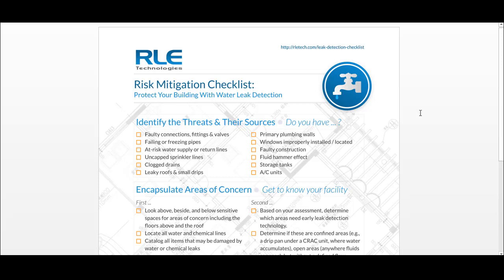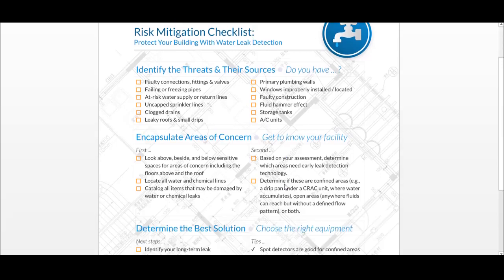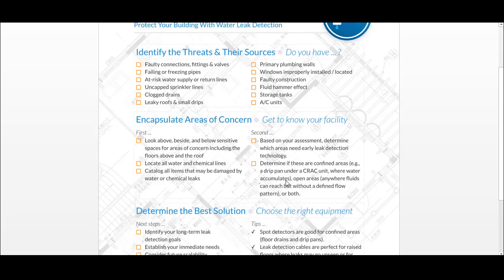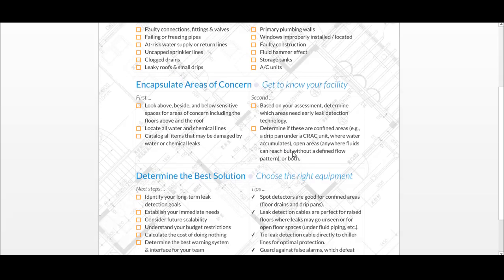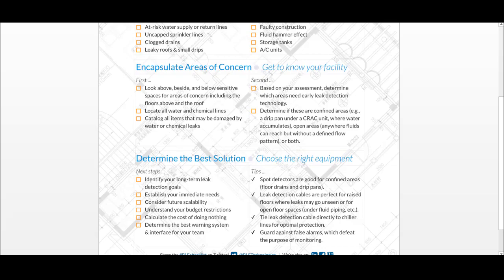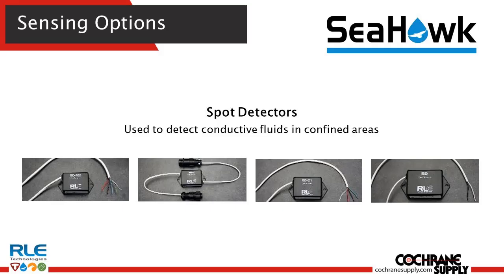Is plumbing in the walls? Is there faulty fittings? Is there valves? Have you had problems with it? What's the age? Are there uncapped sprinkler heads? Could there be clogged drains? What happens? Leaky roofs, small drip pans, and then start to look at, well, where does it go and what happens if it does go, right? So are we looking at a drip pan type solution where a spot detector could work? Or are we looking at something where it may require some sensing cable and a longer range of sensing options?